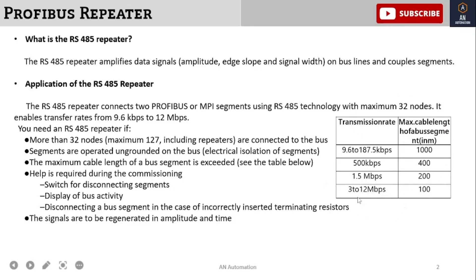Here is the tolerance level chart for better understanding. At 3 to 12 Mbps speed, 100 meters is the maximum cable length — after that you will have to put a repeater in the line. At 1.5 Mbps, the maximum is 200 meters; at 500 kbps, 400 meters; and at 9.6 to 187.5 kbps, up to 1000 meters cable length can be used.